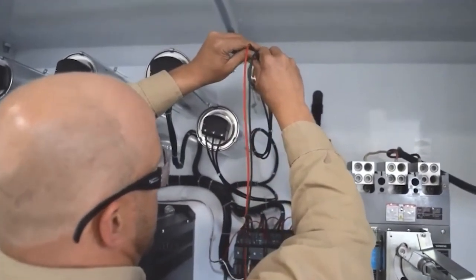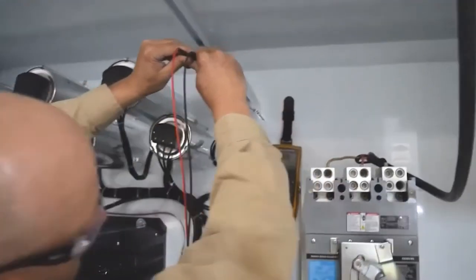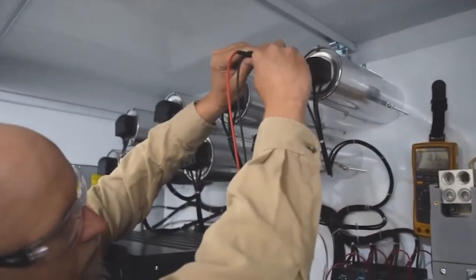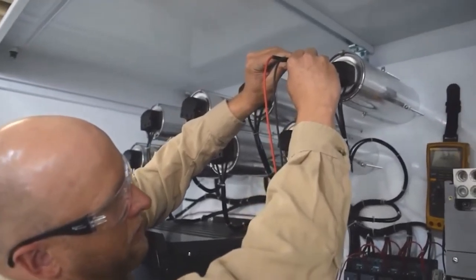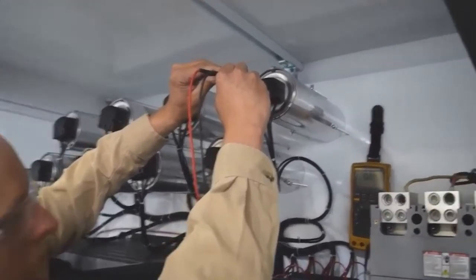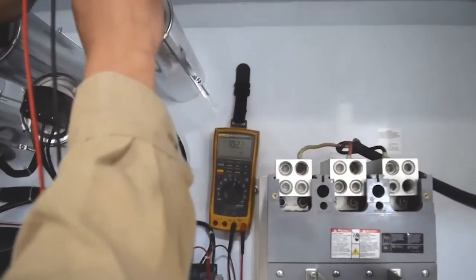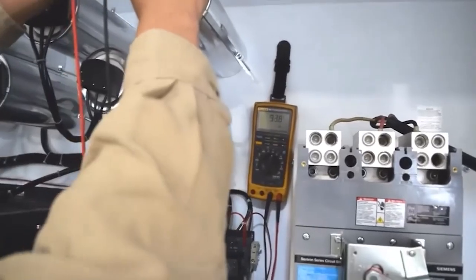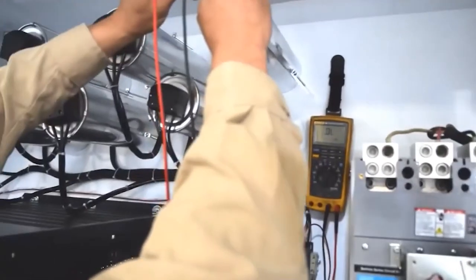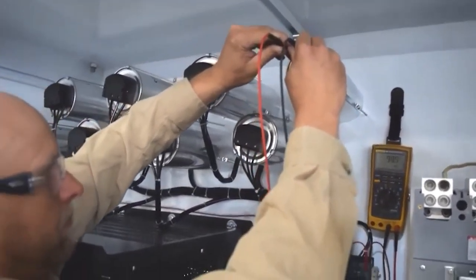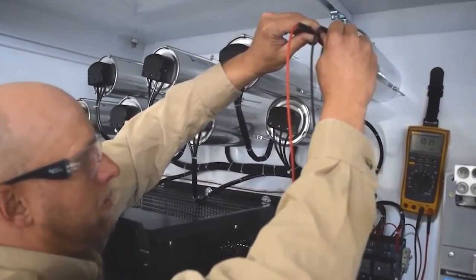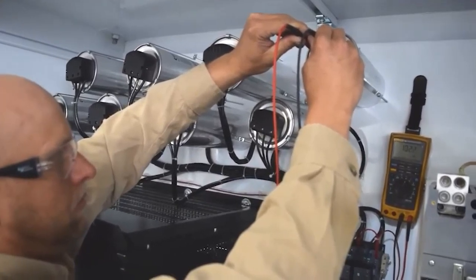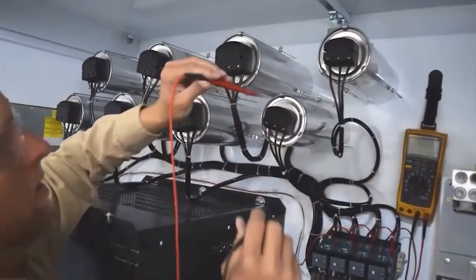Now this particular capacitor, I'm measuring in microfarads. I'm measuring about 102 microfarads. What I'm going to do is measure it from A to B, and you've got to leave it on for just a minute because it'll charge up the capacitor as you're taking the reading. So it'll start lower and then work its way up to 102 and then flatline and stay there. You see how it hit 96, I think, when it started, and then it quickly rose up and got to a 102 reading. That's a normal thing for a capacitor to do. What I'm looking for is that on A to B, B to C, and C to A, they're all the same reading. If I have any kind of a very large variance, it's an indication that the capacitor has a problem.